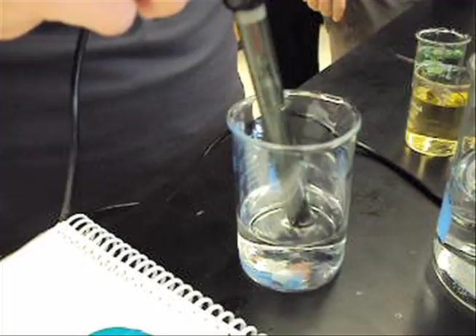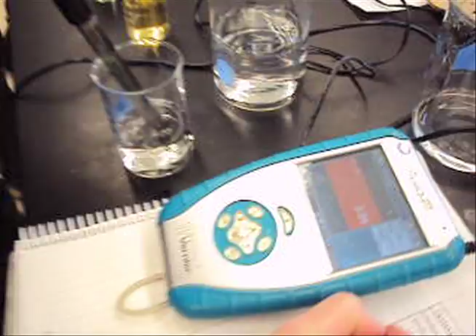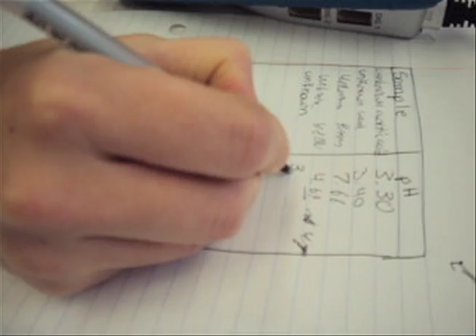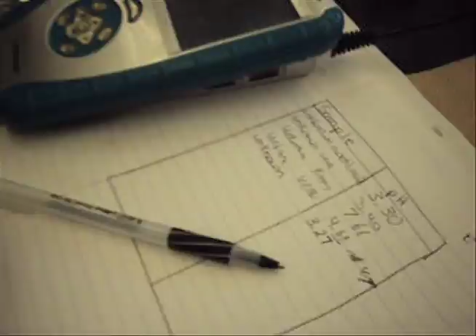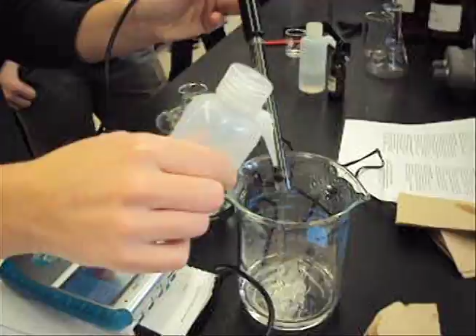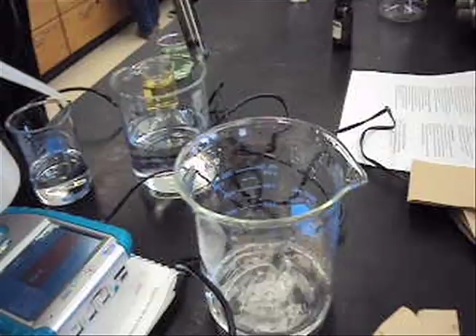Swirl it and wait for the pH to stabilize on the meter. The slope of the horizontal line is always going to be 0. So once it stabilizes, record it in your data table to all significant figures given from the meter. Take it out, rinse it, rinse it completely, and place it back in the deionized water.